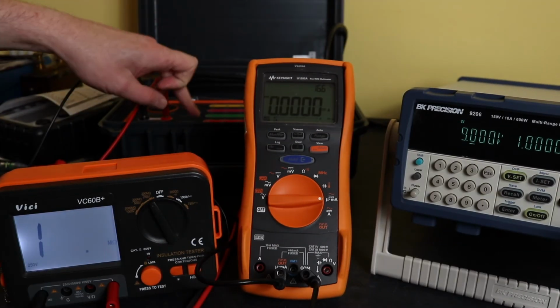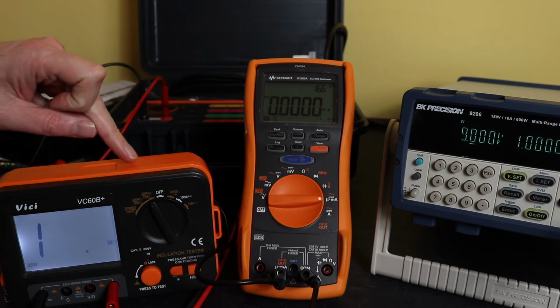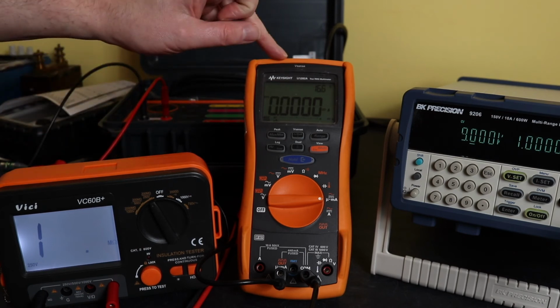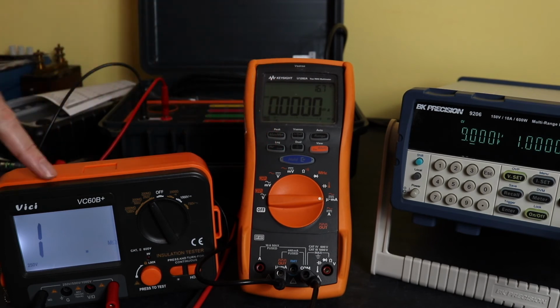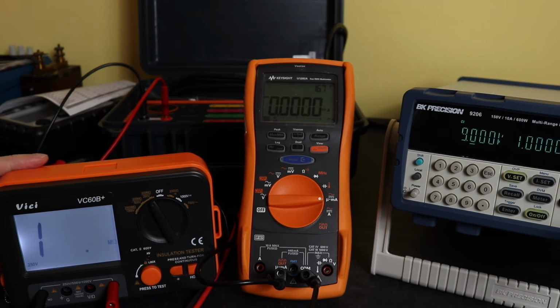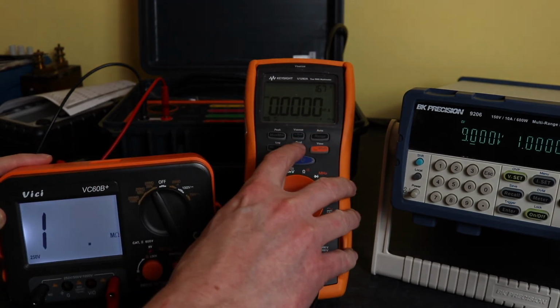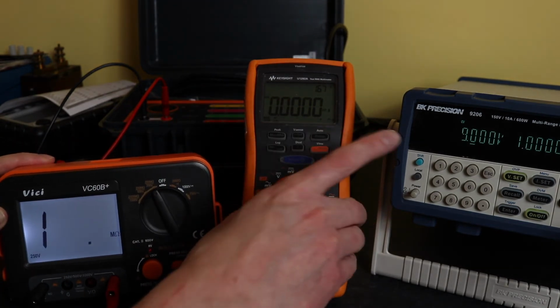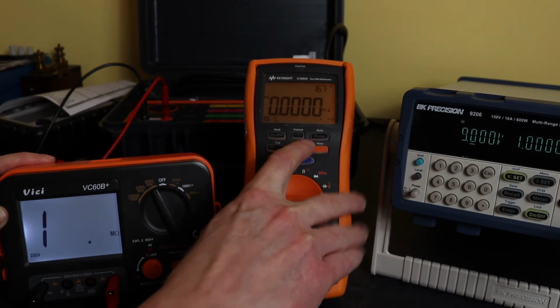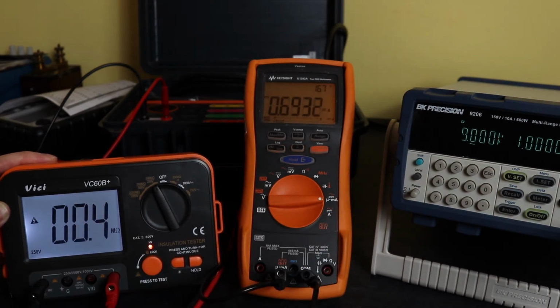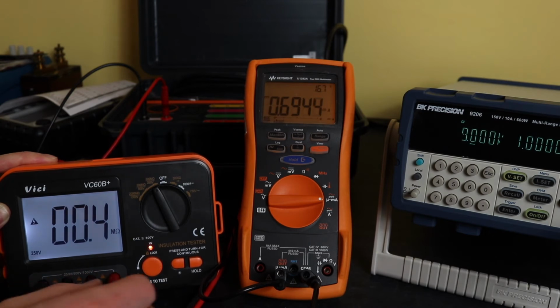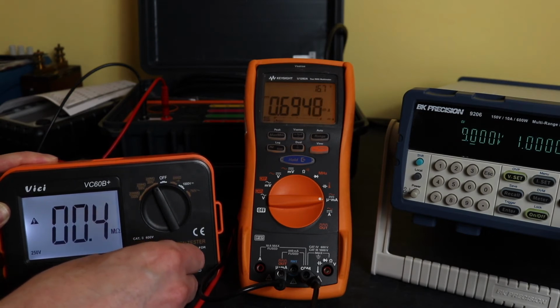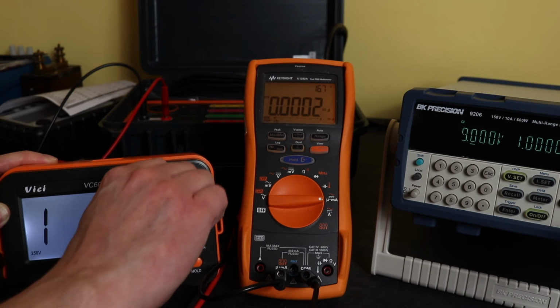Okay, so I now have a load bank connected into the output of the insulation tester now, and converted this to an ammeter. I'm going to measure the current flow. We are at 250 volts, 250 kilo ohms, so I should now get 1 milliamp on this instrument. When we hit the go button, my battery voltage is back up to 9 volts, and we can see we can only get 0.693 milliamps out of the tester. So that's another failure. It should be 1 milliamp.